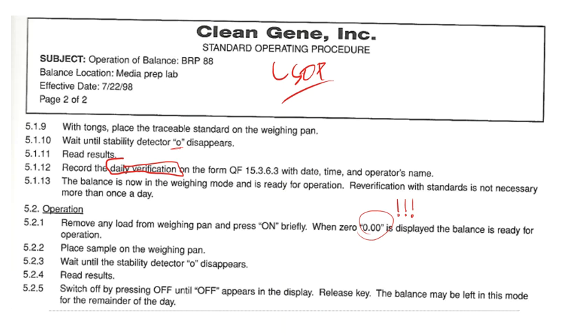All right, so next one says the balance is now in the weighing mode and you're ready for operation. So for the operation, this is just an SOP to talk to us about how we can go through and measure out something on a balance pan. So it says remove the load from the weighing pan, make sure it's zeroed or tared, then place your sample on the pan, then wait for the stability detector to disappear, then read the result, and then if you're finished, press off. Turn the balance off, so that way it doesn't waste energy and it doesn't use the electronics component of the balance. Walk off, leave it, have it ready for someone else when they need it as well.